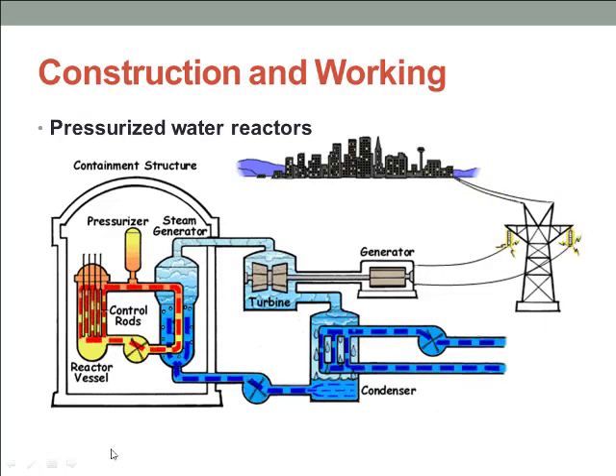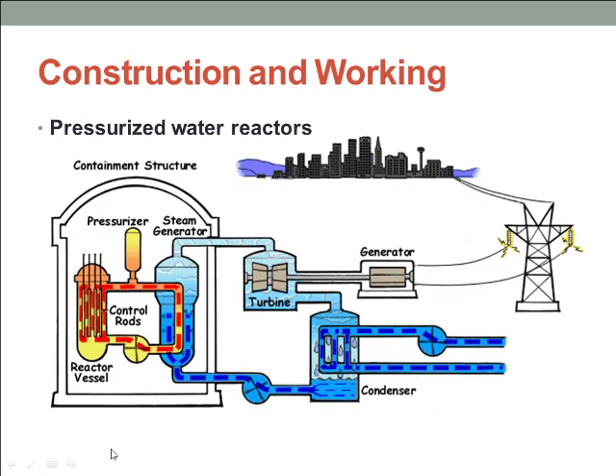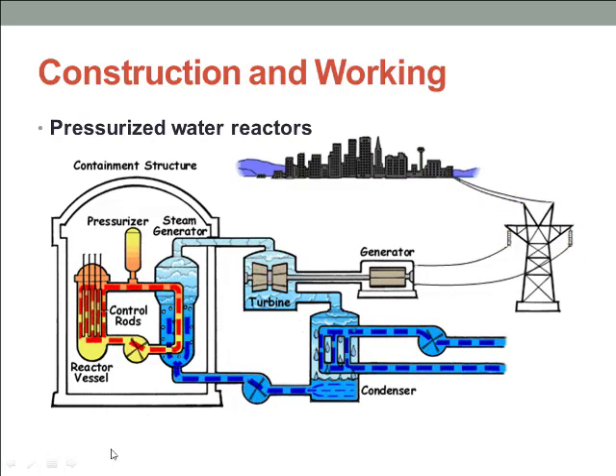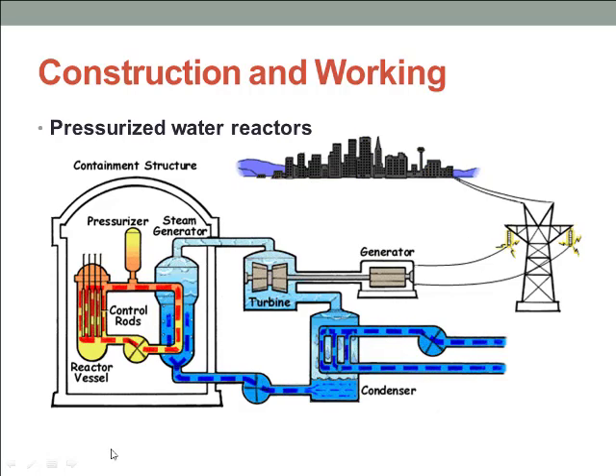The hot primary coolant is pumped into a heat exchanger called the steam generator, where it flows through hundreds or thousands of small tubes. Heat is transferred through the walls of these tubes to the lower pressure secondary circuit. The transfer of heat is accomplished without mixing the two fluids, to prevent the secondary coolant from becoming radioactive. In this way, the primary and secondary cycle water remains separated — in the primary cycle, high temperature is achieved due to higher pressure conditions, but the water does not physically leave that chamber; only heat is transferred to the secondary cycle.